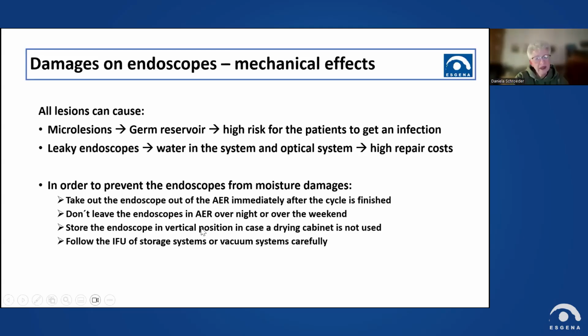If you don't have a drying cabinet with single ventilation of all channels, please store the endoscope in a vertical position. I hope that gravity will work and all drops will come out. Maybe not, but it's the first step to motivate the endoscope to become drier. And please, if you use a kind of vacuum system so that you can store it for a longer time, please read the instructions for use.